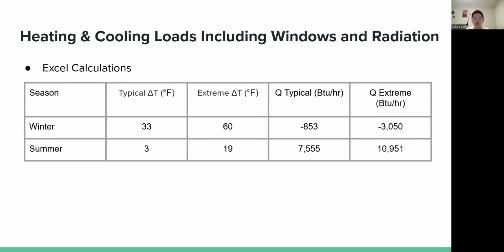Besides just using the basic Excel tool to get R values for all of our envelope components, we created a more advanced iteration of this tool that lets us analyze the heat transfer through our envelope, including windows, and getting a more comprehensive R value using parallel series calculations. We also included heat transfer due to radiation through the windows. This results in a heat loss of about 3,000 BTU per hour in the winter and a heat gain of about 11,000 BTU per hour in the summer.